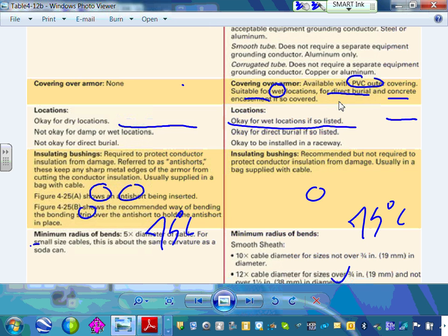But if you want to go underground with a feeder, you don't want to use PVC conduit; you could use MC cable with a PVC cover, rated for wet location. It will be an expensive solution compared to PVC conduit and wires. Why wouldn't you use it? Expensive solution. Okay, so that's location. Let's look at the location.